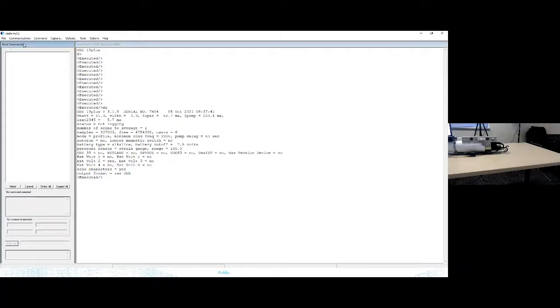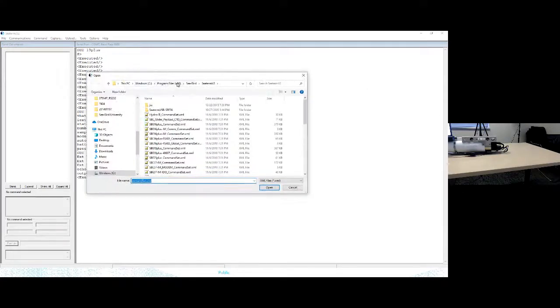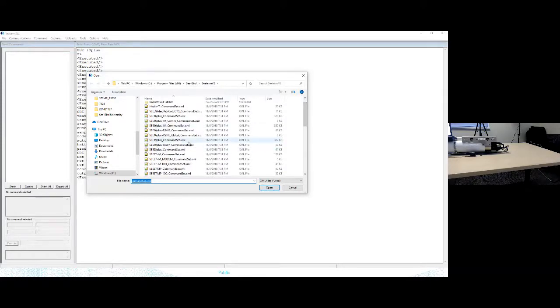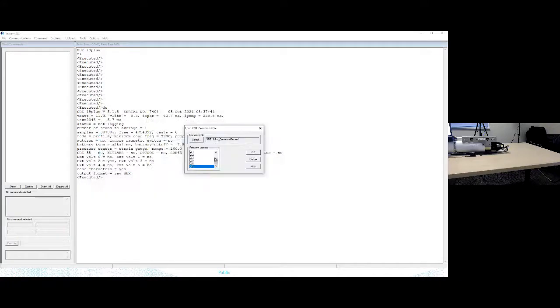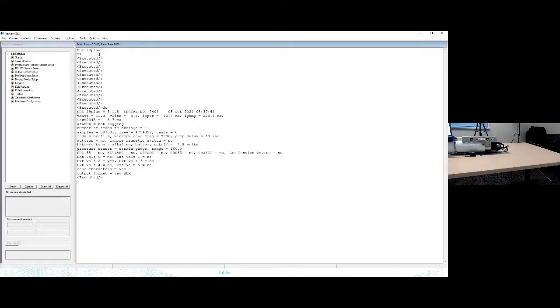Sometimes Seaterm does not populate the send commands window, and that's okay. Normally it fills in with all the commands that apply to your instrument's firmware version. If it's not populating, go to File, Load Command File, and within the program files for SeatermV2 there's a list of command files in XML format. We're going to open the 19 Plus command set XML, specify firmware version 3.1, and click OK. From there it populates the send commands window.